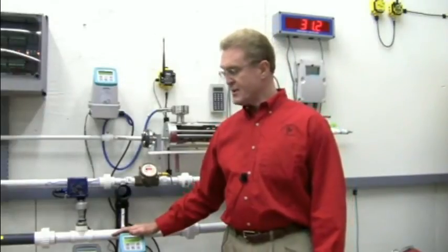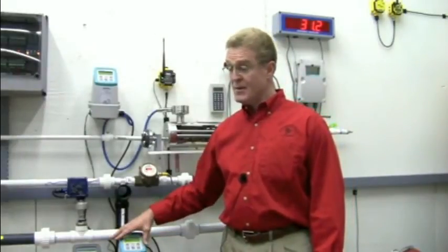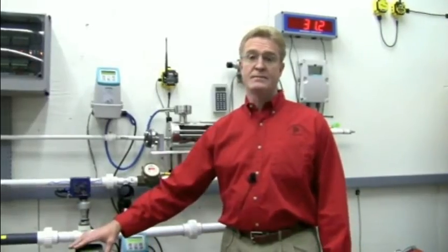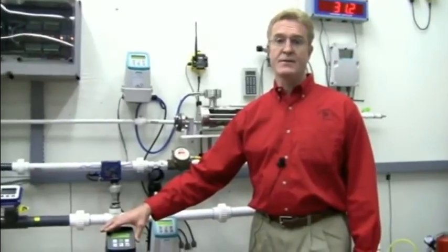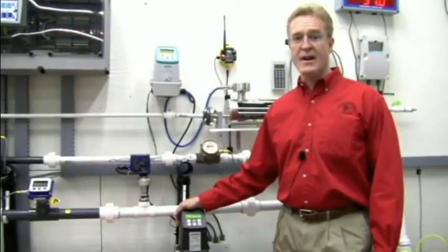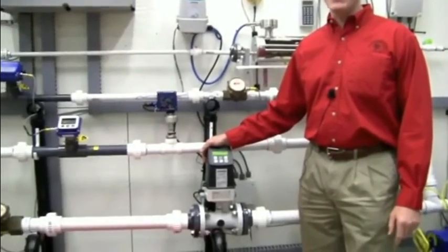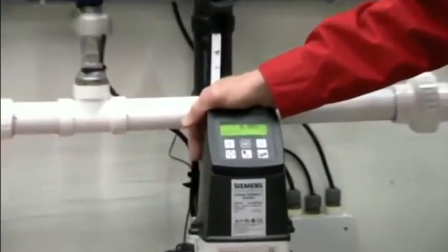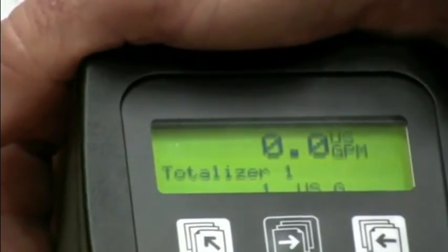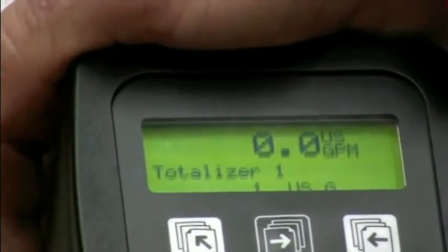I'm going to replace the beige transmitter rating in gallons with the black transmitter presently rating in liters. As you can see, the black transmitter now powers up reading both sensor characteristic and setup data, and we're back up and running with the original units set for the flow lab meter—gallons per minute and totalizing in gallons.